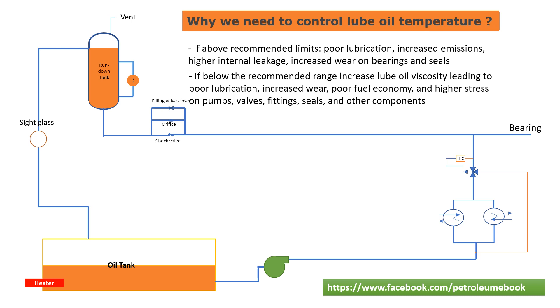Hot fluid will activate the thermal actuator, causing the internal cartridge to close and forcing the fluid through the system cooler. When the lube oil temperature is increasing, the three-way valve will open more at the cooling side to get more cooling medium to reduce temperature.